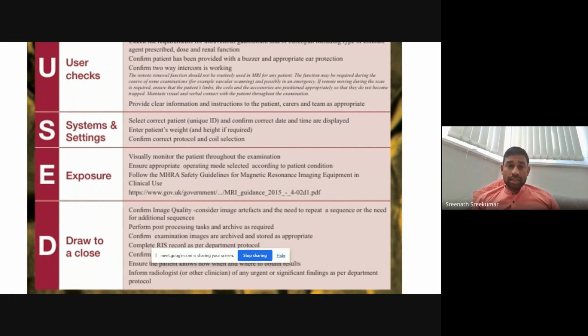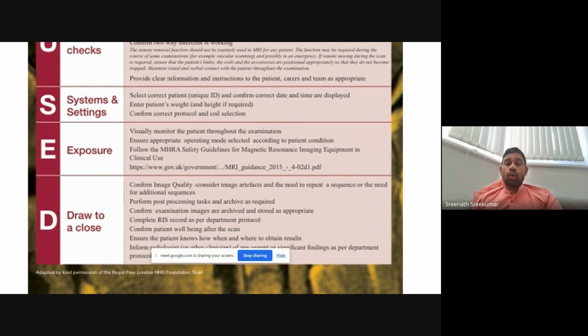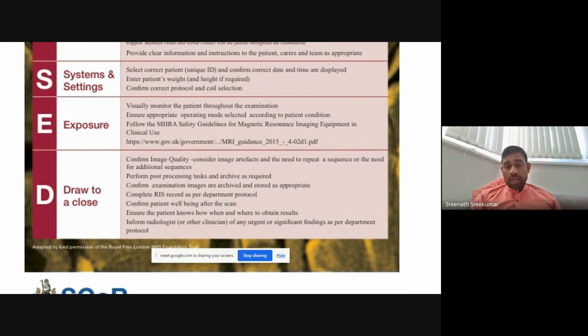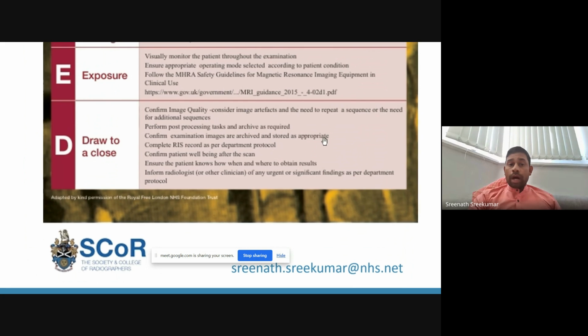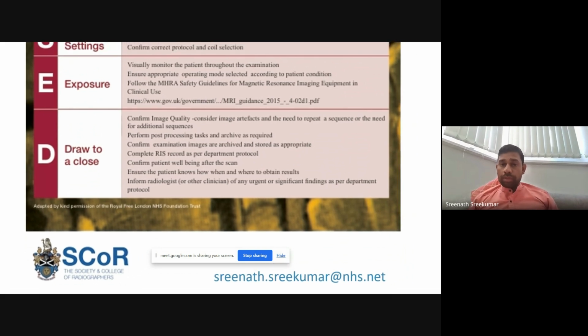Then we have to check the system has the ID and the patient's weight, which is very important from the SAR point of view, and confirm the protocol and coil selections are clearly done. On exposure, we follow the MHRA guidelines to give the specific energy dose or SAR limits for a particular kind of scan, like normal mode or first level mode. After the scans, we should confirm the image quality by checking the images and confirm they are accurate, without motion or artifacts, or whether we have to repeat.